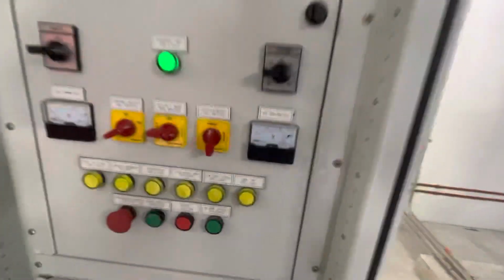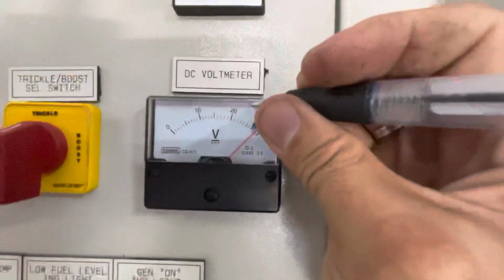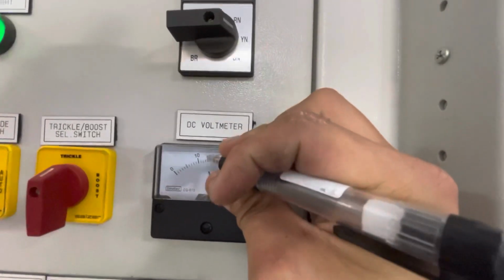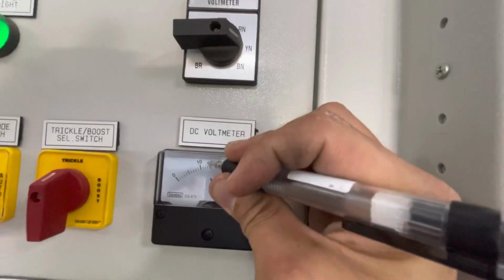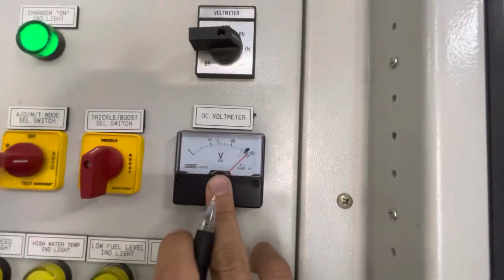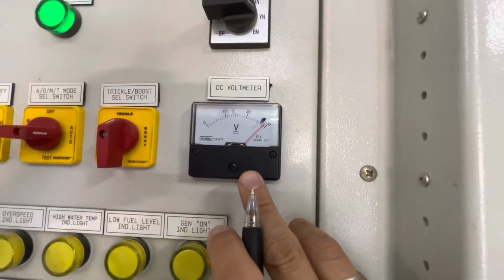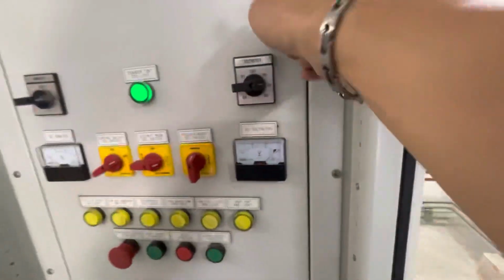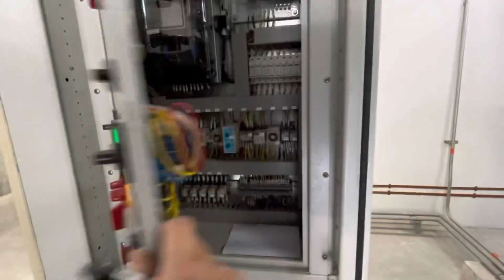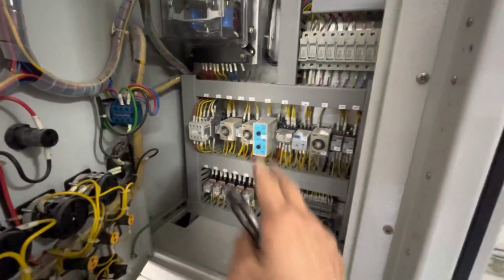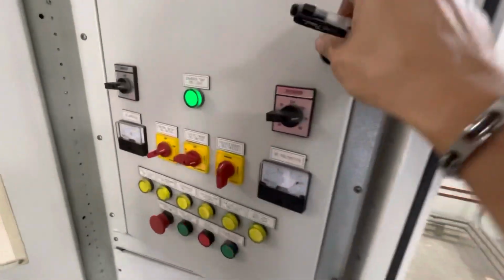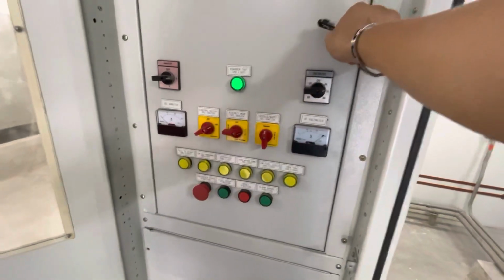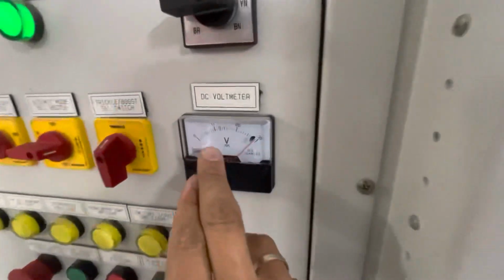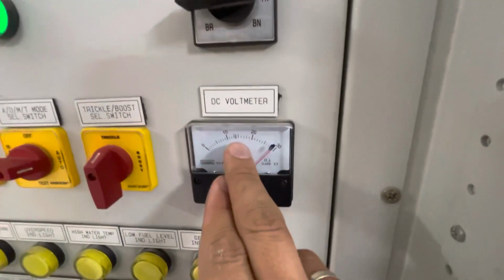Okay, before we test run, we're going to put a reference point here, 15 volt DC. Why do we use 15 volt DC as a reference point? Because most of the 24 volt DC parts, items, relay, contactor, control card, once the voltage drops below 15 volt DC, it will release and reset and malfunction because the voltage drop is too low. So we use 15 volt DC as the reference point.